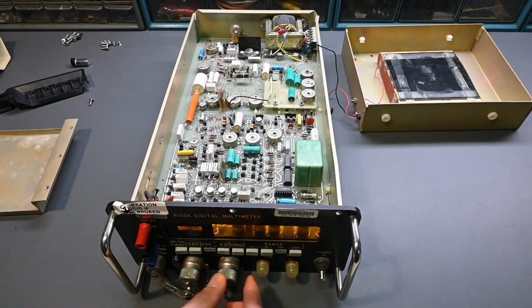I think these got broken when something hit the front out here and damaged them. But electrically, they may still work. I'll take a resistance reading through them and see if there's continuity, and I don't see anything causing a short circuit. They haven't been twisted around or damaged wiring on the other side. So it may be possible in pretty short order to power this instrument up and get a better idea of the condition, and see exactly what's going on electrically with it.